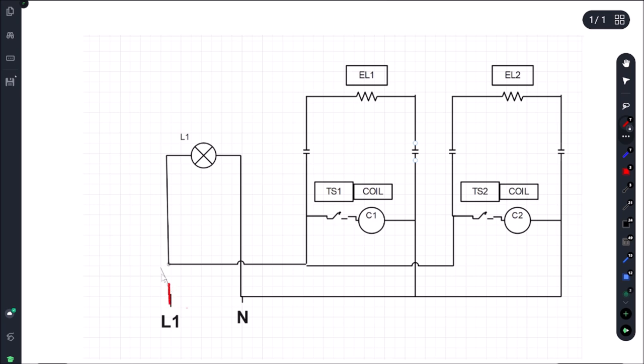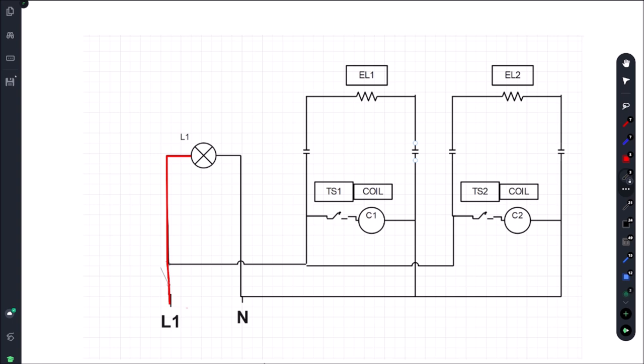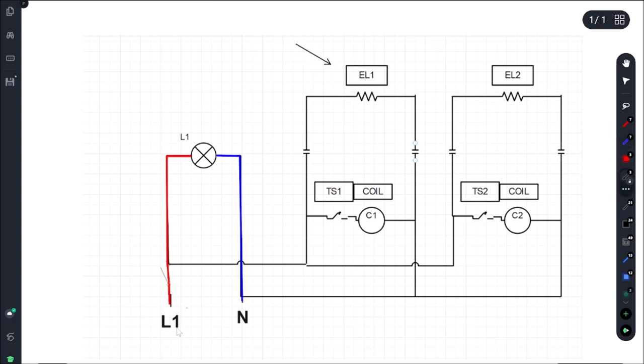For the light circuit: as soon as we get power from our main switch, it closes — I just call them bridges. Once that bridge is closed, we have a straight shot. Where people get stuck is they'll test to ground. If you test this point to ground you're going to get 120 volts and think the light's bad, but you need your neutral. This becomes more important with 208/240 single phase or three phase — you cannot test things to ground. Neutral is a straight shot, no bridges, no switches.